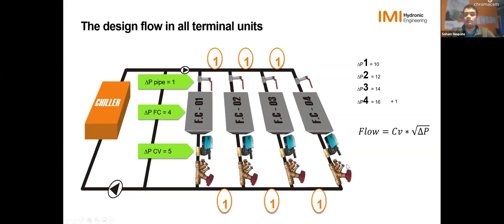So as per ASHRAE, we want to have 1 feet of pressure drop on our index unit. So that's what we size this valve for. We have 1 feet of pressure drop on that manual balancing valve added to the circuit. That gives us a total pressure drop of 17. So now we know that we have a total differential pressure here of 17. And to have that equal differential pressure in each of these, 1, 2, 3 as well, we're gonna add just the right amount of resistance to get to that 17 for our differential pressure. And that's how, with the manual balancing valves, we're basically able to get equal differential pressure in your system, and thus take over that risk of overflowing or underflowing your terminal units, okay?